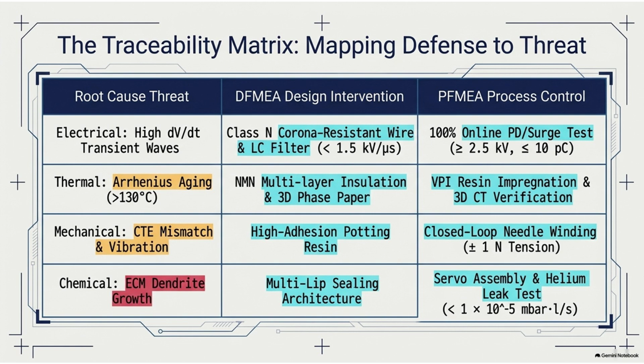Exactly. And once the pristine wire is successfully wound into the motor, it has to be locked into place with a liquid resin. Right, to stop the vibration. But you can't simply pour resin over it and let it dry. Yeah. The source dictates a mandatory process called vacuum pressure impregnation, or VPI. This part of the source material was fascinating to me because the entire goal of this complex VPI process is to eliminate air bubbles.